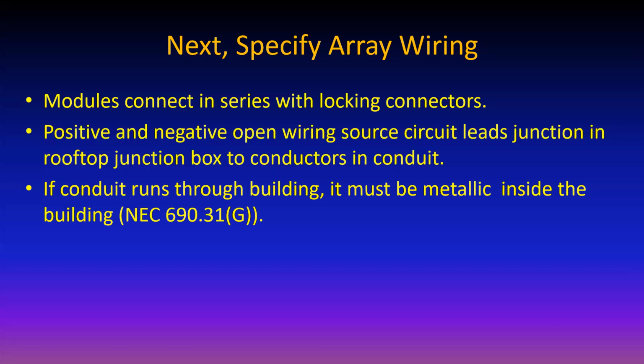Conduit runs through a building. See, from the rooftop junction box, you then splice the open circuit wiring to conductors in the conduit. And then you need to do some derating due to the temperature on the roof and the number of conductors in the conduit and so forth.